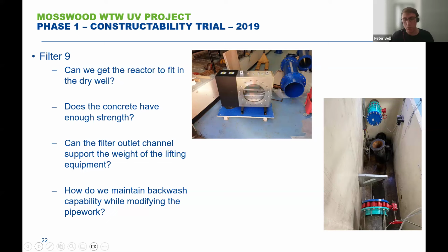And with that come a lot of challenges with the pipework. We had to configure the pipework in such a way that it would introduce some hydraulic losses. So we needed to understand what those hydraulic losses were likely to do to the site flow. Were they going to majorly affect it? What would that look like? One being introduced, then 12 of these being introduced. We then had to consider the pipework support. So the concrete that was holding the pipework, does that have the right amount of strength? Is the floor strength suitable? There were no thrust blocks in, but we needed to put thrust blocks in, pipe supports, all those different types of things.